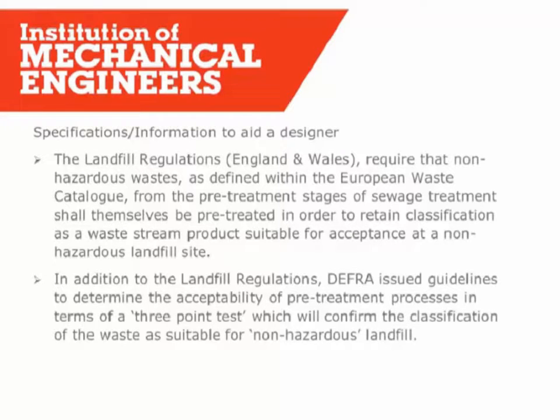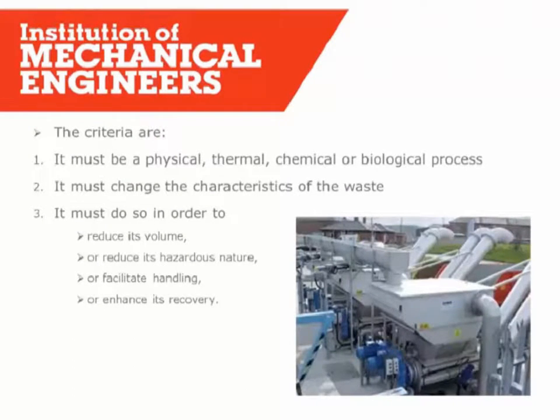Furthermore, we have the landfill regulations. These require that non-hazardous wastes as defined within the European Waste Catalogue from the pre-treatment stages of sewage treatment shall themselves be pre-treated in order to retain classification as a waste stream product suitable for acceptance at a non-hazardous landfill. In plain English, you've got to do something to the screenings you remove in order to dispose of them to a non-hazardous landfill site. DEFRA has issued guidance on this in the form of a three-point test: the process must be physical, thermal, chemical or biological; it must change the characteristics of the waste; and it must reduce its volume, reduce its hazardous nature, facilitate its handling, or enhance its recovery.